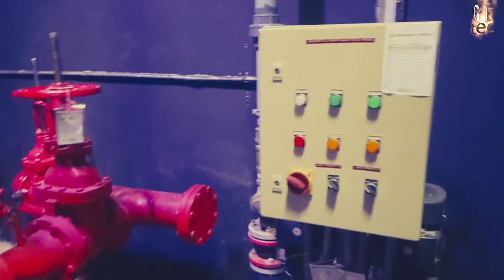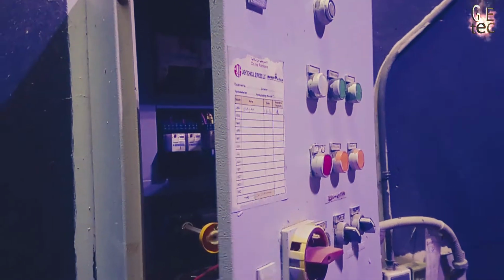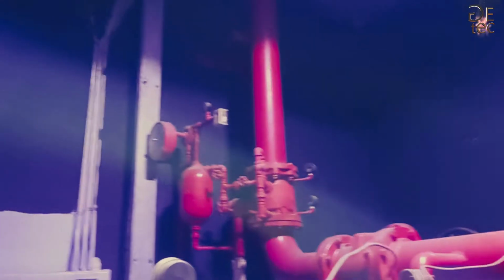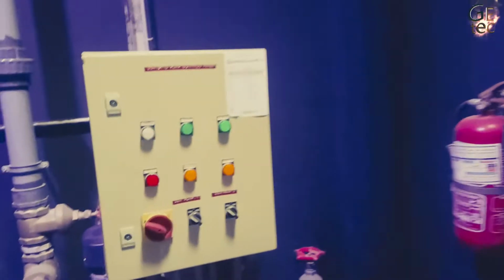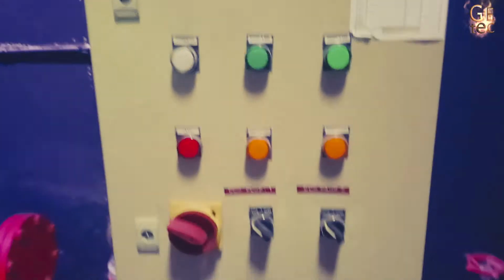The fire pump starts when the pressure in the fire sprinkler system drops below a threshold. The sprinkler system pressure drops significantly when one or more fire sprinklers are exposed to heat above their design temperature, and opens, releasing water. Alternately, other fire hoses, reels or other firefighting connections are opened, causing a pressure drop in the firefighting main. Fire pumps are needed when the local municipal water system cannot provide sufficient pressure to meet the hydraulic design requirements of the fire sprinkler system.